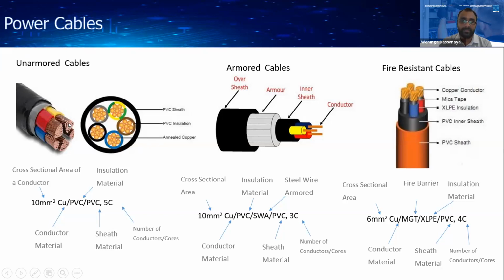So if you are indicating this kind of unarmored cable in a single line diagram or a drawing, you have to use this type of notation. You can see the first one is 10 square millimeters. That means the cross-sectional area of a conductor inside this cable. Next, Cu means copper. That means the conductor material. What is the conductor material? As I mentioned, it can be an aluminium cable. If it is an aluminium cable, Cu will be replaced by Al to denote aluminium. So mainly we have two types of cables, copper or aluminium. So this is the conductor material.